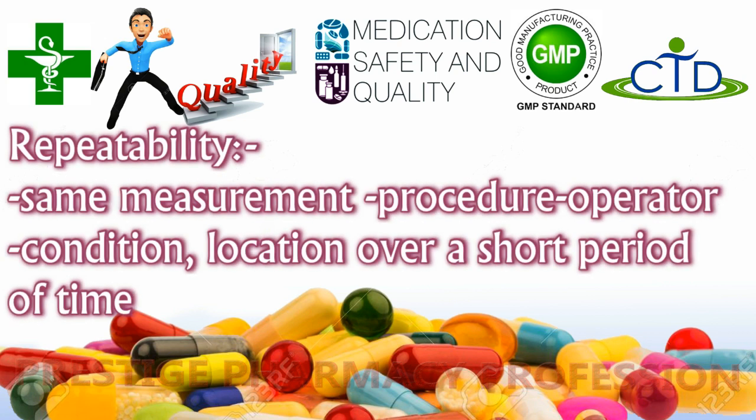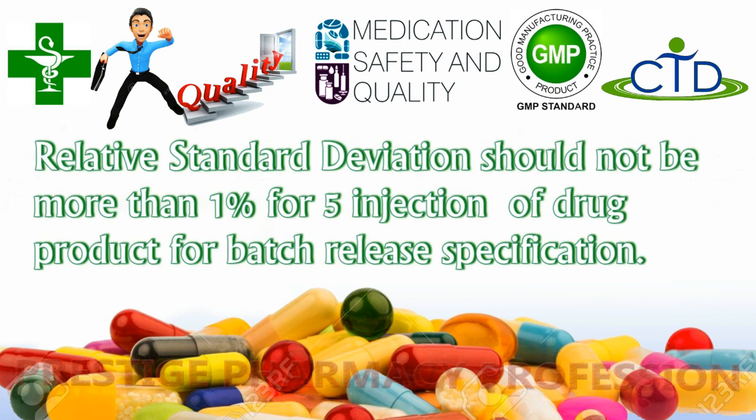Repeatability is determined by the relative standard deviation of the peak areas of chromatograms obtained in the same laboratory, by the same operator, using the same machine and the same sample. The relative standard deviation should not be more than one percent for a minimum of five injections. If the relative standard deviation values stay within the prescribed limit, the method is validated and accurate to use.